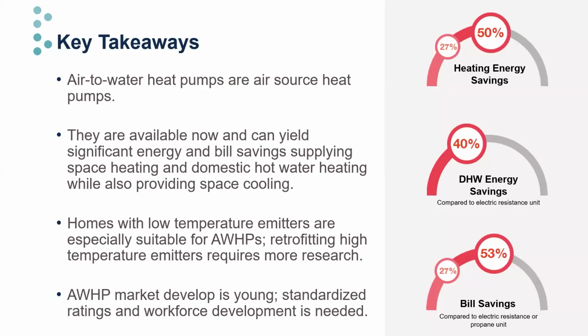In our study, we focused on low temperature radiant slab emitters because we're concerned that retrofitting high temperature emitters, like cast iron radiators that are designed for supply water temperatures as much as 160 degrees, might struggle to supply the load when the supply water temperature from the air-to-water heat pump is only like 120 degrees. But yeah, the savings are significant, and this is a great opportunity to get in early.